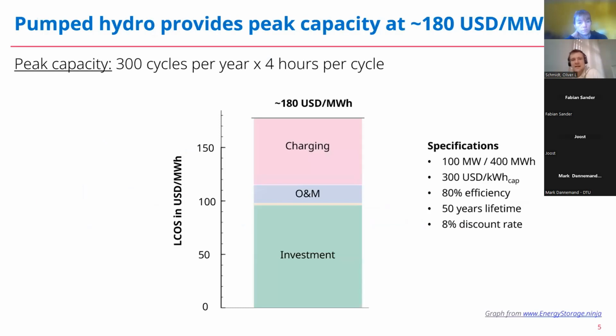What I've done here is calculate the levelized cost of storage for a pumped hydro system in an application that I will call peak capacity. More importantly, it has 300 cycles per year, where it discharges for 4 hours per cycle. The specifications are on the right. I've assumed a 100 megawatt, 400 megawatt hour system. The capex is around $300 per kilowatt hour, 80% efficiency, 50 years lifetime, 8% discount rate. So this pumped hydro system will discharge electricity at $180 per megawatt hour.